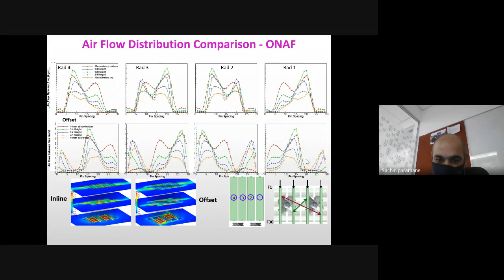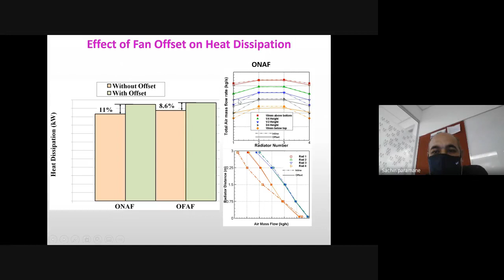So a comparison of heat dissipation is made, and it was observed that by just offsetting the fans by 300 millimeter in both the directions, we are getting improvement in the heat dissipation by 11% in ONAF and 8.6% in OFAF. So you can see the comparison for ONAF total airflow. Dashed line is inline and solid line is offset. So towards the end radiators, due to fans offsetting, the total air mass flow going in between fins increases with the offset fans.